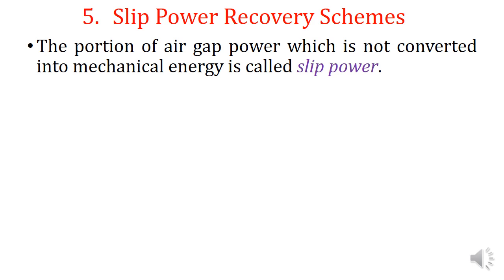In the previous lecture we discussed the rotor resistance control, in which the slip power was wasted in the external rotor resistance. By controlling the amount of power wasted in the external resistance, we were controlling the speed of the induction motor. Instead of wasting the slip power in the external resistance, here we are going to feed the slip power back to the source.